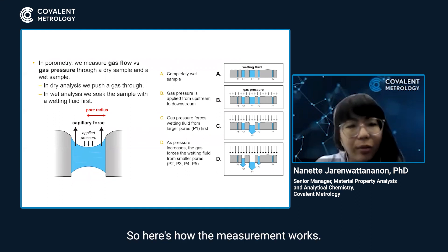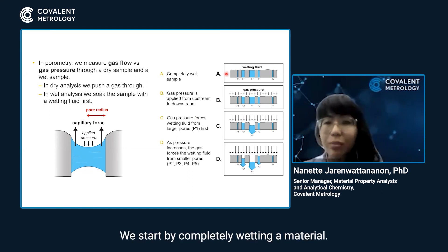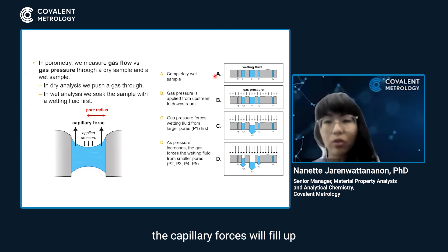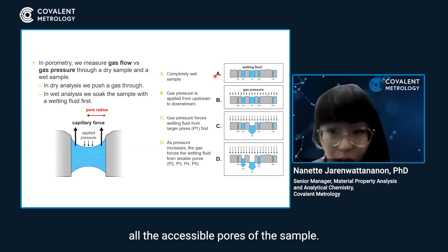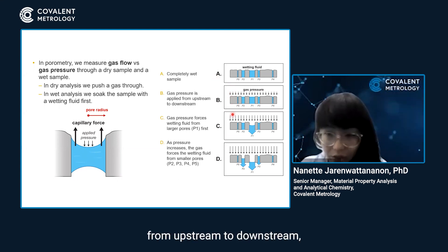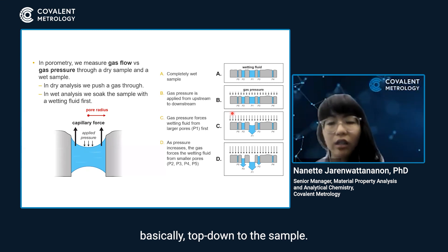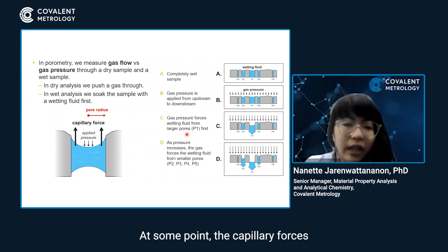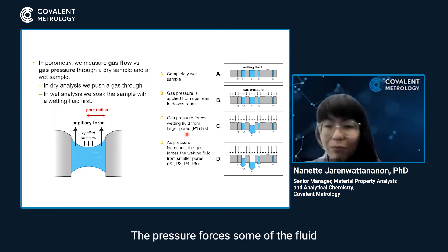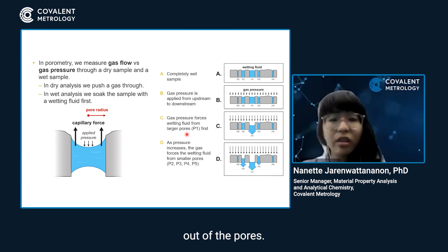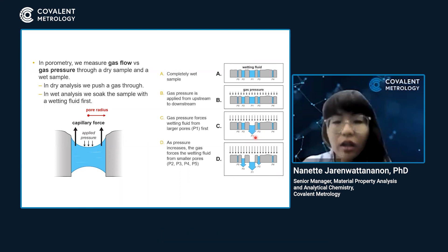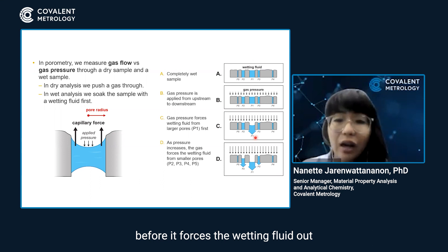Here's how the measurement works. We start by completely wetting a material. The capillary forces, if we saturate the material, will fill up all the accessible pores of the sample. Once the sample is completely wet, we apply a gas pressure from upstream to downstream — basically top down to the sample. At some point, the capillary forces are overwhelmed by the gas pressure. The pressure forces some of the fluid out of the pores, and the gas pressure is going to force the wetting fluid out from the larger pores before it forces the wetting fluid out from the smaller pores.